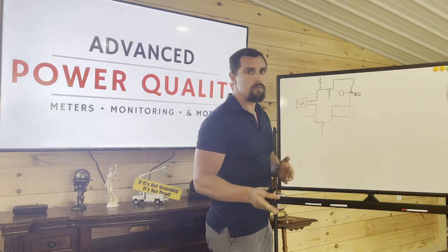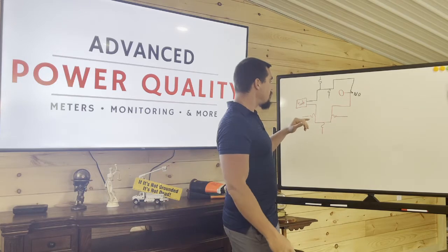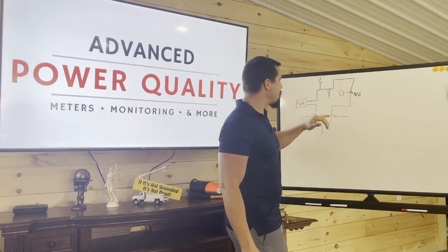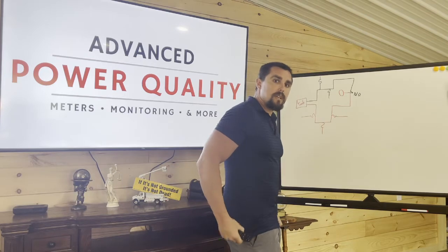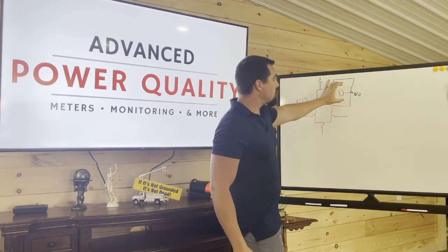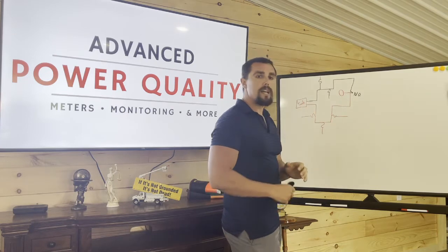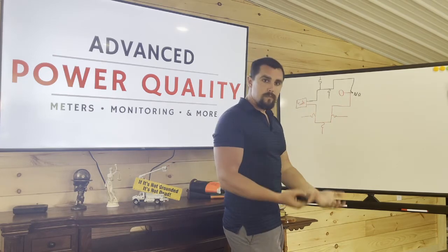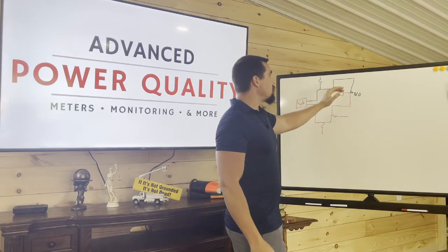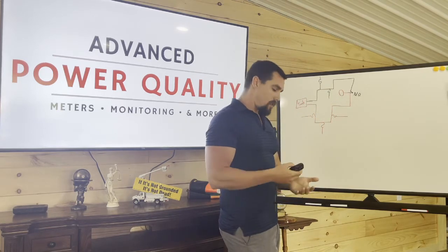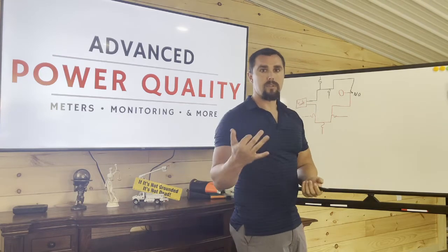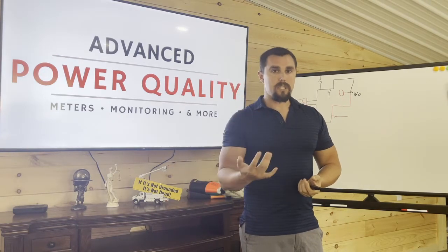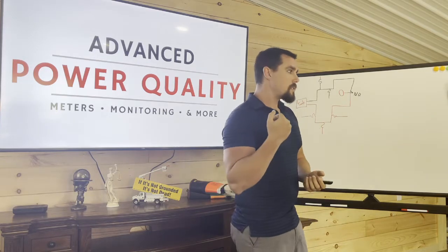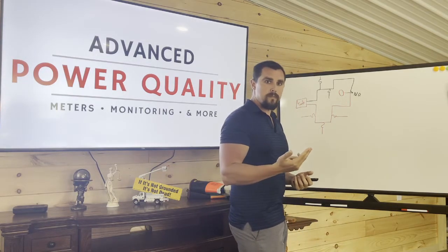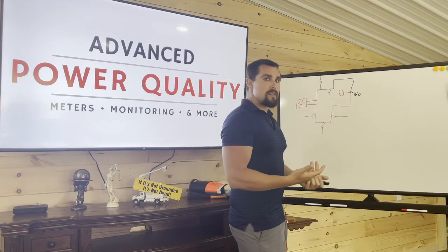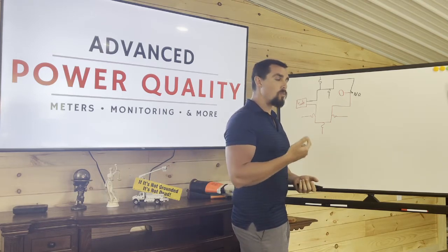Now, one other thing I want to bring to our customers' attention is, let's say red feed has 2 or 3 capacitor banks, black feed has 2 or 3 capacitor banks. Well, same scenario, utility has to transfer the customer to the black feed. Well, as I was saying earlier, fuses blow, outages happen. Utilities have those capacitor banks, and essentially a capacitor bank has cells per each phase. There's fuses per each phase going to those cells. Now let's say 1 or 2 fuses blow and the other one doesn't. That capacitor bank is still online, but it's only doing the work for one phase.